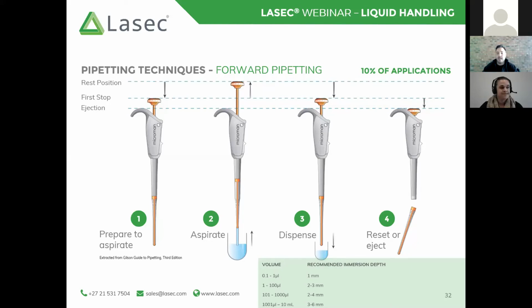Because we are not working with air anymore, we are working with a physical piston that's going to aspirate and dispense. It's going to forcefully suck up and physically push out that sample. I no longer need a stop that's going to push additional air to force that sample out of the pipette. So this is why you don't have a second stop as with an air displacement pipette. Instead, they've replaced that stop with an ejection button. This also is a built-in ejector, so it allows you to pipette out of tubes, things that are generally quite difficult to pipette out of with normal air displacement pipettes.